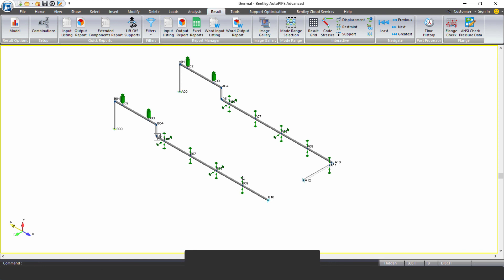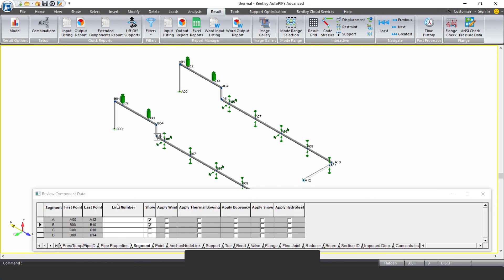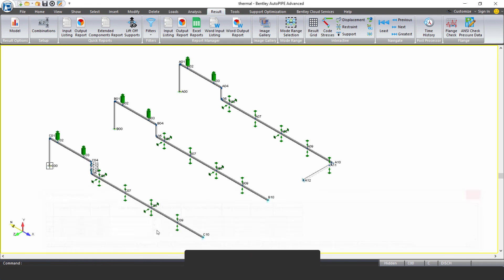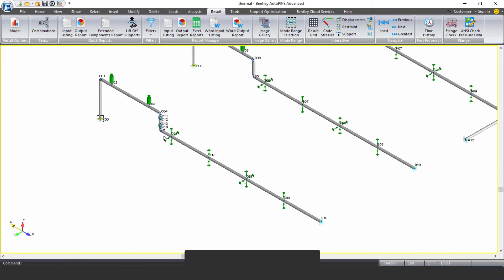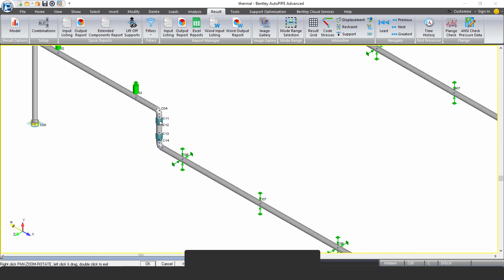We could maybe model our configuration a little bit differently and add hard pipe flexibility by adding in a deeper or another expansion loop, a z-bend, or maybe putting the original bend back in. We can allow flexibility. But if we can't and we have a pipe like this, we can use some expansion joints. So if I turn on my C segment, that's just what I've done here. We have the same pipe, but we've added some expansion joints here.